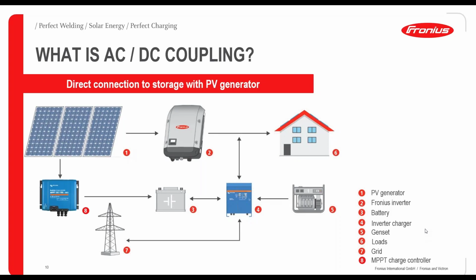A next step would be AC and DC coupled, which is a combination of both advantages, including DC coupling. You see again the same scheme as before with the AC coupling and the inverter charger of Victron and our inverter. Now the MPPT charge controller of Victron comes into the scheme. The PV generator is split up: one part goes to the Fronius inverter, and the other part goes to the MPPT charge controller of Victron, directly connected to the battery.